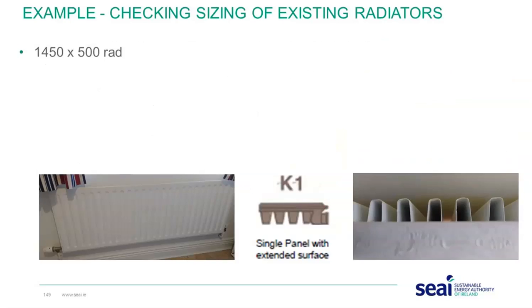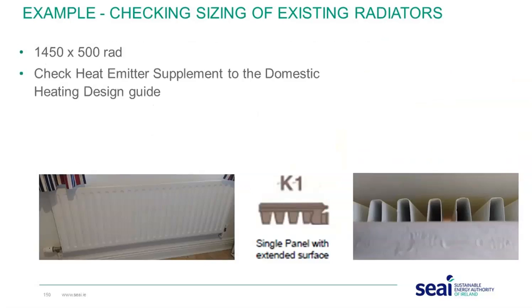So I have an example here. We have a 1450 by 500 rad. You can see it there from the image, a single panel convector. I checked the heat emitter supplement to the domestic heating design guide, and it tells me that at a delta T of 50, it will give me 1,179 watts.